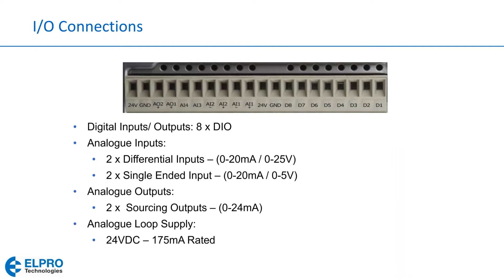For the I/O connections for 4 to 20 milliamp inputs and outputs and voltage signal inputs and outputs: first, we have 8 DIO labeled D1 through D8. They can function as inputs or outputs, but obviously not at the same time. Each digital point has an LED right next to it, so you can look at the LED to see whether the I/O point is active or inactive.